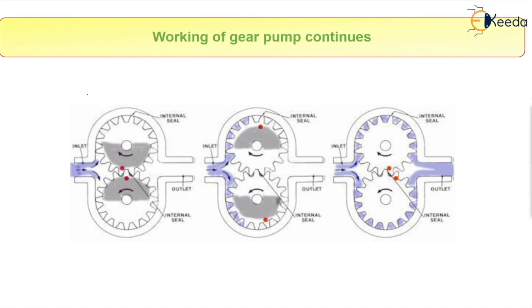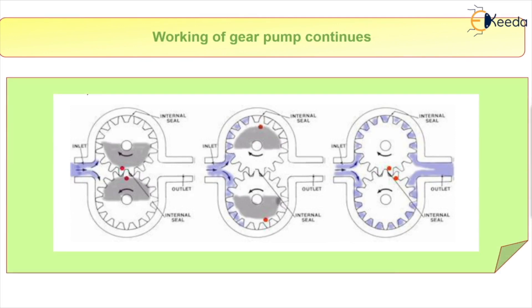How exactly does the external gear pump work? In phase one, the liquid enters. Both gears rotate — one clockwise, one anti-clockwise — and two seals prevent liquid from flowing directly across or returning. In phase two, the liquid travels in the spaces between the gear teeth. These spaces, similar to the internal gear pump, move the fluid continuously along the casing wall. In the final phase, the fluid is forced to move out through the outlet. This is the working of a gear pump.